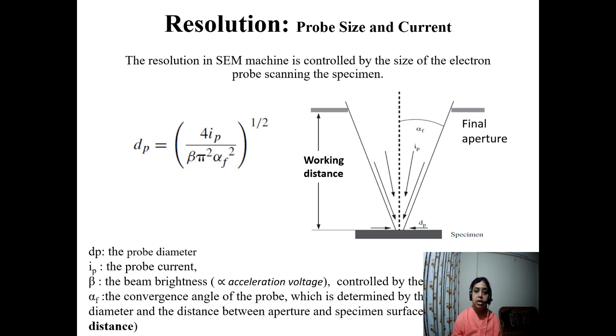So here is the expression for the probe diameter. This is the area at which the electron is hitting the sample. This is the probe current which is flowing, the amount of electrons going into the sample. Again, beta is the beam brightness. This is generally controlled by the accelerating voltage as well as the electron source. So generally there are different kinds of guns.